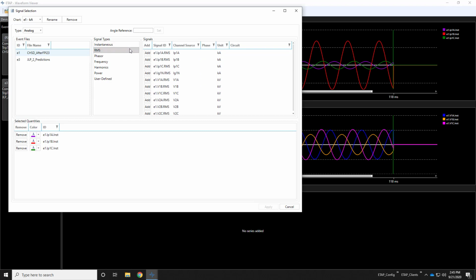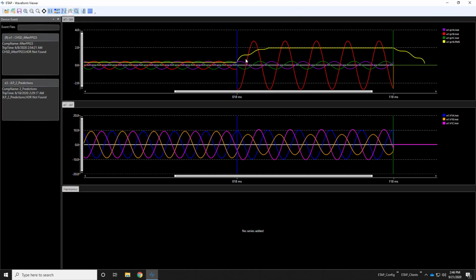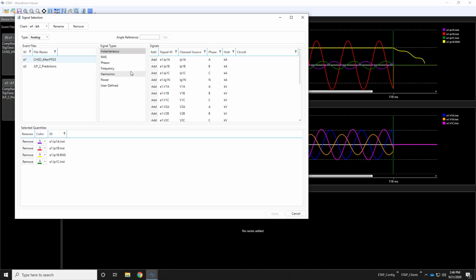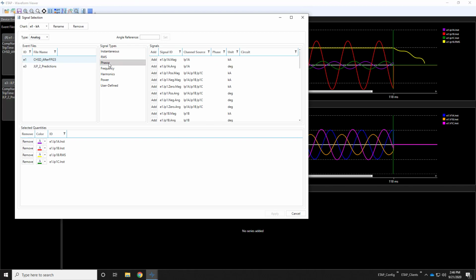So for instance, I'm going to bring in my B phase RMS value into that view. I'm going to change the color to yellow to make it more obvious and hit apply. And now you can see the RMS value here for that B phase. So my B phase RMS value is based off of my B phase instantaneous current. Additionally, we can bring in many other different calculated values. For instance, phasor values, my positive, negative, zero sequence data, my frequency information.